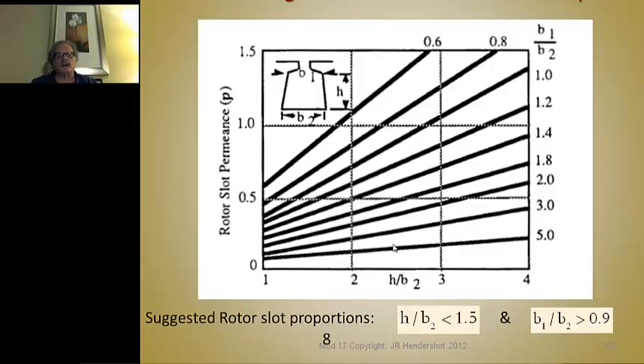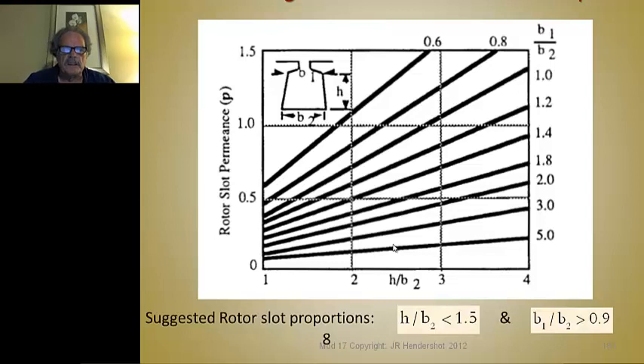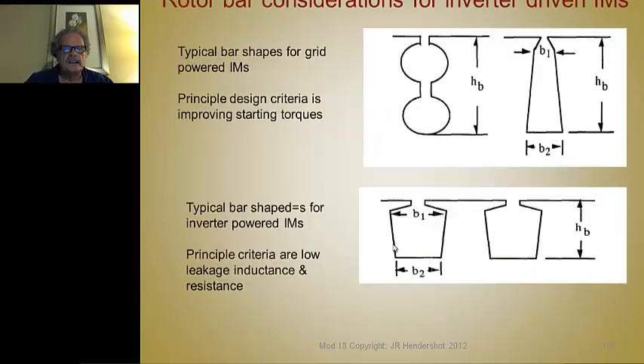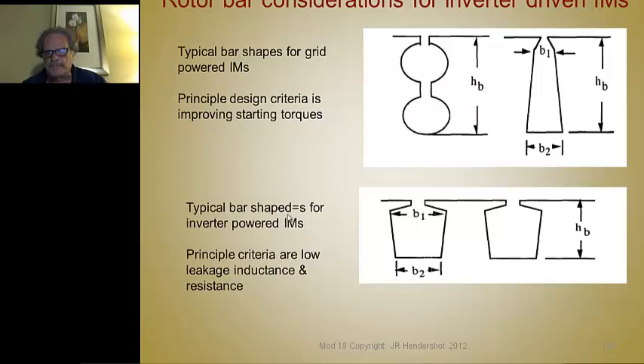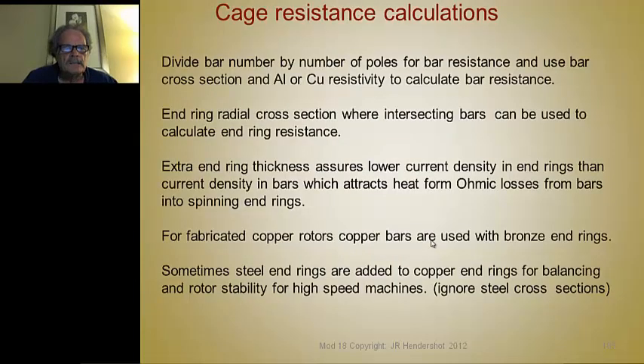Here's a plot of rotor leakage as a function of rotor slot shape — I believe this came from Lipo's book — showing suggested rotor slot proportions, which can be very helpful for design. Here are also some bar shapes. The double bar at the top — there's no good reason to use that. These are the typical bar shapes we'll use for inverter-driven machines.